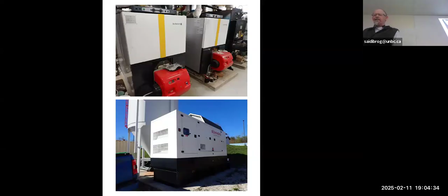And this is what we call a magic H, which is an exchange loop with a three-way valve that allows you to schedule the secondary water through the secondary pumps by opening or closing, modulating this valve. So in summertime you can have low temperature water, and in wintertime high temperature water. Now there's a shadow on it, but this is actually the schedule.